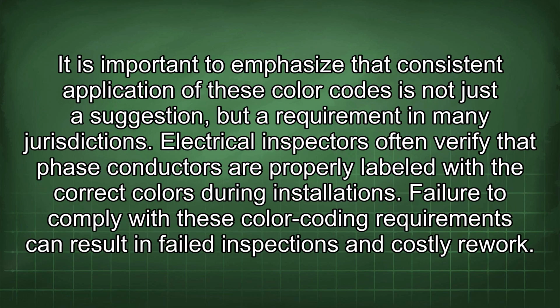It is important to emphasize that consistent application of these color codes is not just a suggestion, but a requirement in many jurisdictions. Electrical inspectors often verify that phase conductors are properly labeled with the correct colors during installations. Failure to comply with these color coding requirements can result in failed inspections and costly rework.